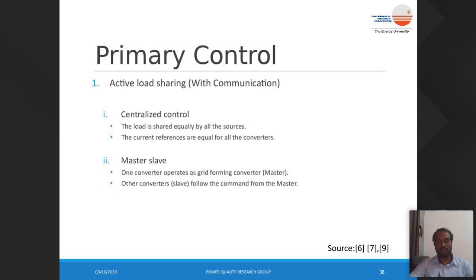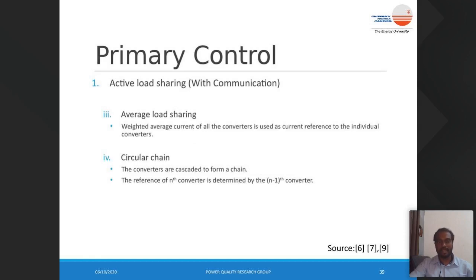In master slave control, we have one grid forming converter, or a master, which sets frequency and voltage reference to all other converters. The other converters follow the command of the master. So this is the master slave topology. We have average load sharing. Average load sharing is similar to centralized control, where the current is shared among the converters, but here they use weighted average current. It's based on the individual converter's reference. It's because in this case the deviation of power or the power injected remains less, as it takes the weighted average current into consideration.